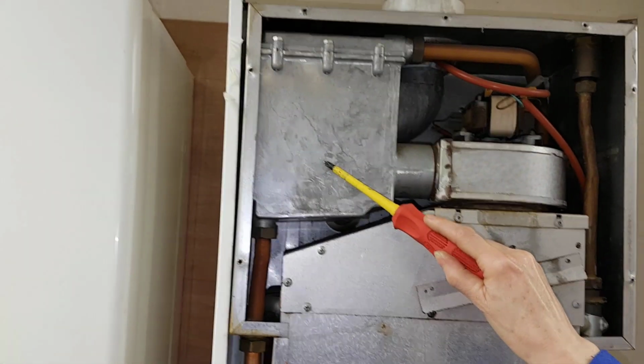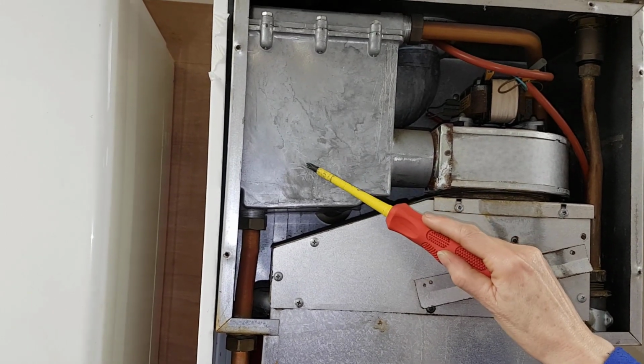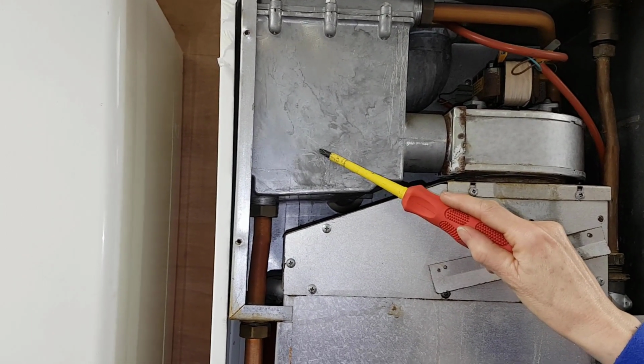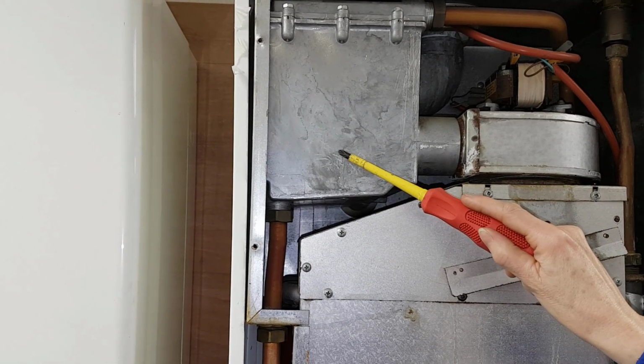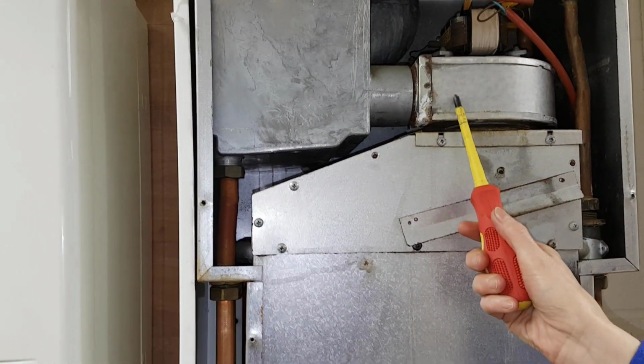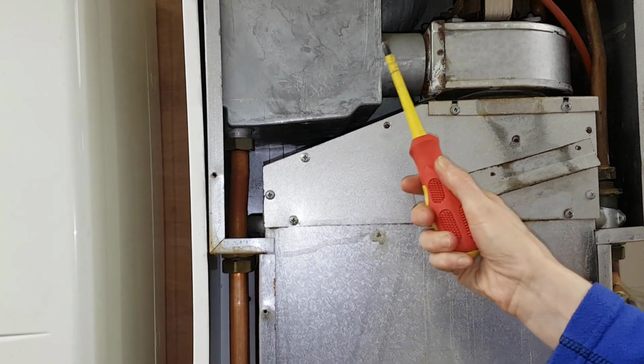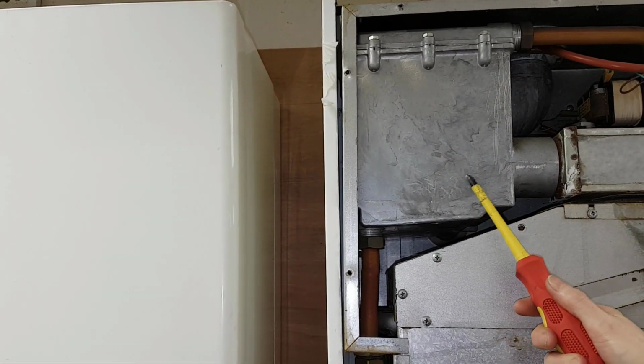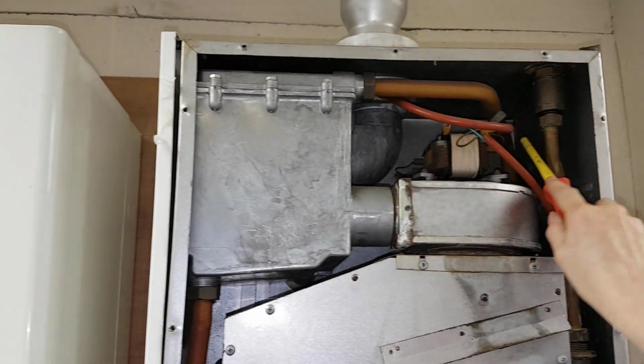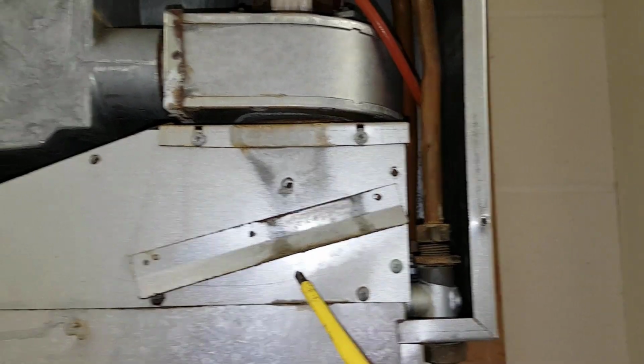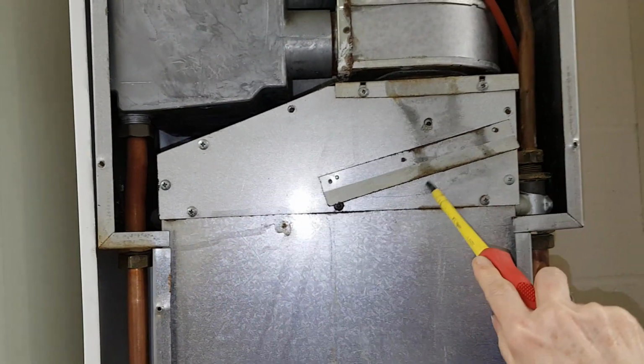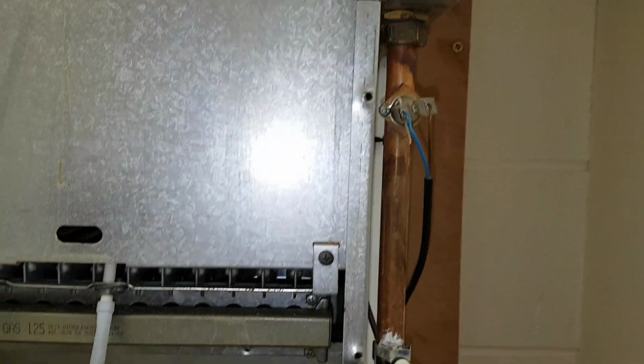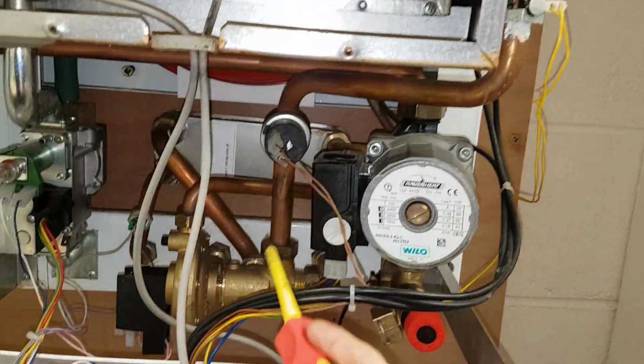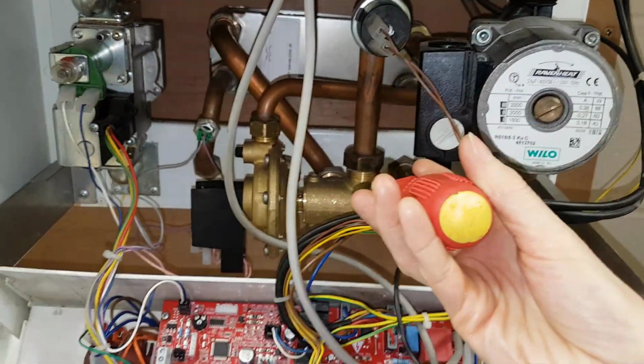Now, a recuperator reheats some of the return water to make this boiler more efficient. The products of combustion from previous ignitions and burning warm this water. As it comes out here, it goes round and down into the main heat exchanger. It then goes round and comes out here as the primary flow. It comes down here, if you follow the pipe round, and back into here.